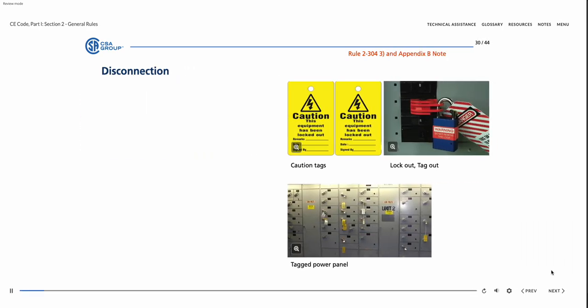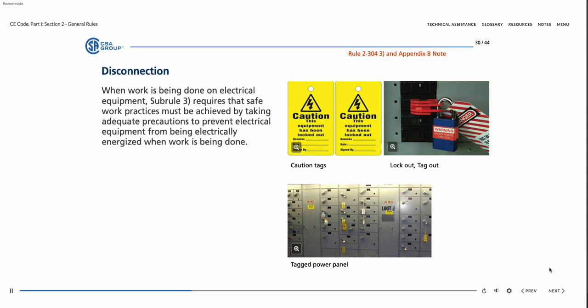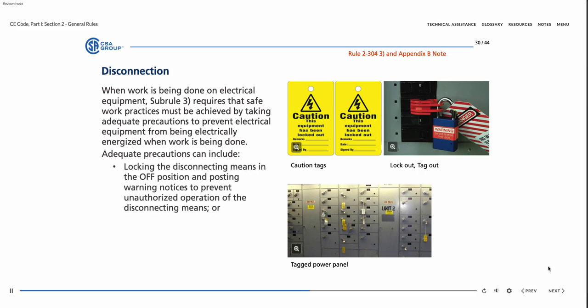When work is being done on electrical equipment, Sub-Rule 3 requires that safe work practices must be achieved by taking adequate precautions to prevent electrical equipment from being electrically energized when work is being done. Adequate precautions can include locking the disconnecting means in the off position and posting warning notices to prevent unauthorized operation of the disconnecting means, or using other equally effective means, including the use of temporary protective grounds. This code requirement is consistent with the philosophy of work-safe practices mandated by the applicable jurisdictional occupational health and safety regulations.